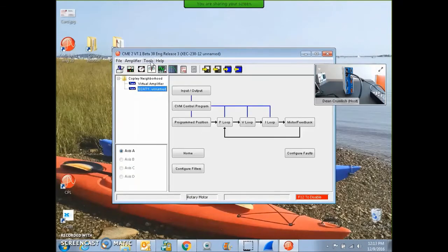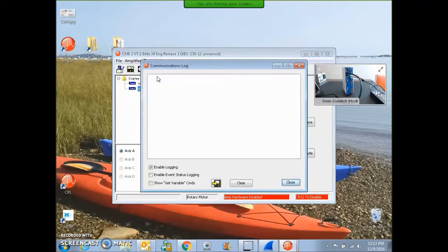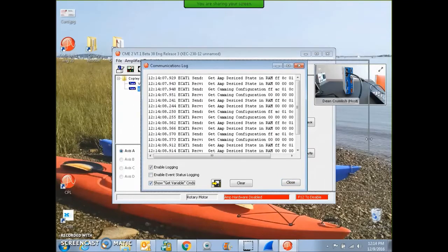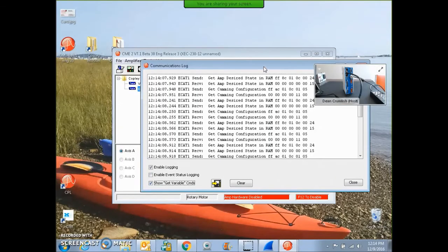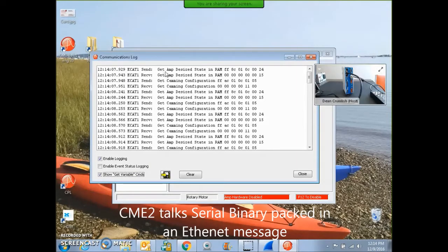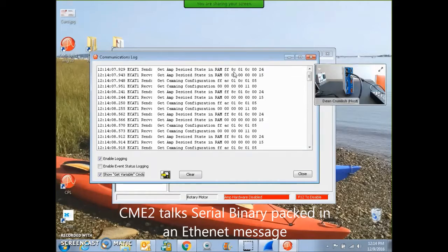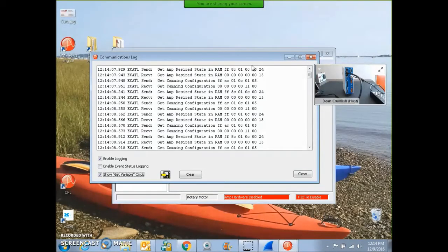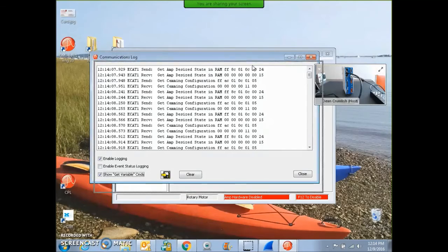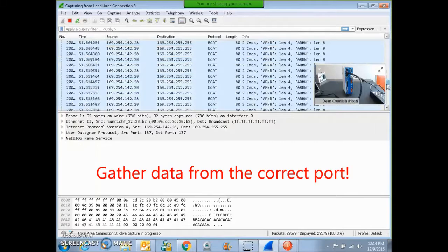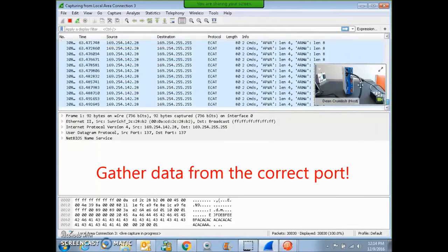Right now, CME2 is communicating with the drive over the Ethernet port and it sends serial binary packets wrapped up in the Ethernet message. For example, send get desired state and it returns back with the desired state. These are serial binary messages sent out over the Ethernet. So the Wireshark should be gathering data for me. Here we go.